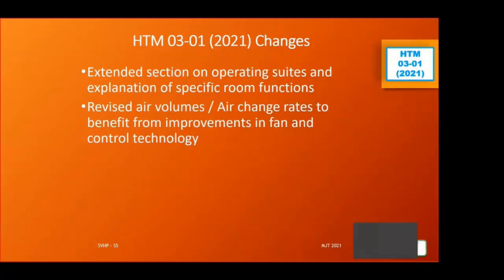We've revised the air volumes and air change rates to benefit from better fans and control technology. We used to want 25 air changes in a theatre, we're now saying 22. It's not that things are getting worse, we only really needed 20. But if you have a belt and pulley driven fan, you need elbow room, because over its life the performance will drop off significantly. If you don't start with a bit of cushion, after a few years you won't achieve the minimum standard you want. Now with better fans and technology we can come closer to what we want, and control the fan's output over its life more accurately, so we use less energy and benefit from the new technology available.